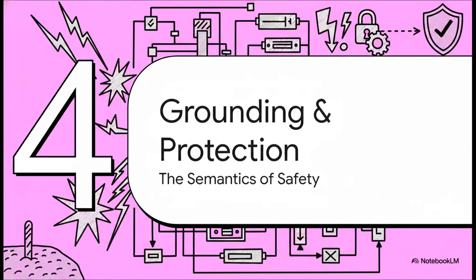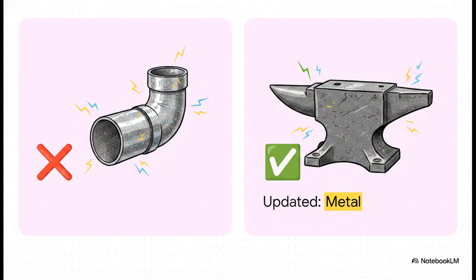Let's switch gears to Section 4, Grounding and Protection, the Semantics of Safety. You know, sometimes the most crucial updates are actually the smallest stylistic ones. Take ground fault. By definition, it's an unintentional electrical connection between an ungrounded conductor and normally non-current carrying parts. But look closely at the change for 2023. They updated the word metallic to metal. It's a really subtle shift, driven by the NEC style manual to keep everything consistent. But it just proves a point. When it comes to electrical safety, being precise with your language is just as important as being precise with your engineering.